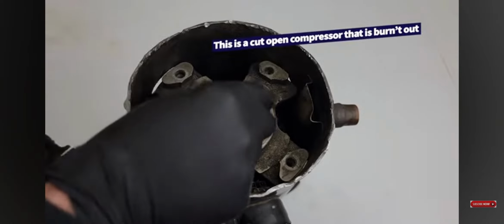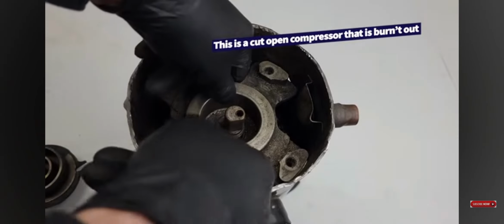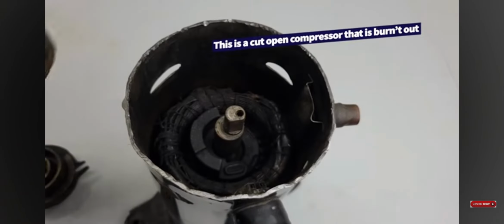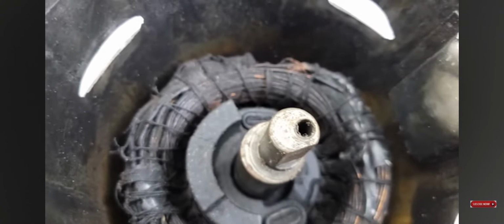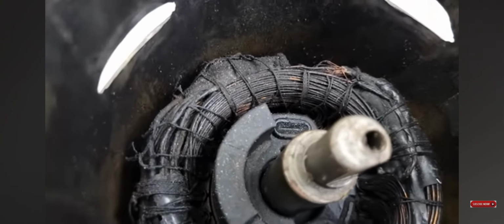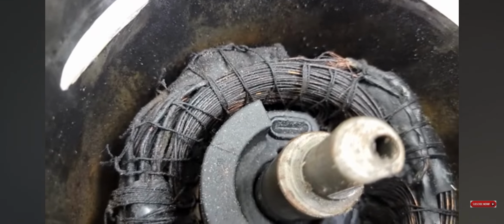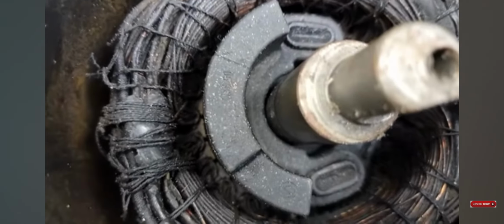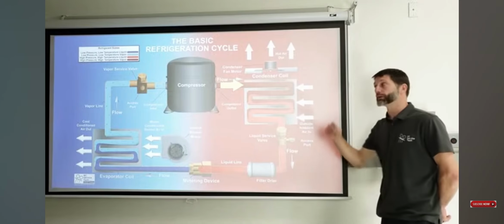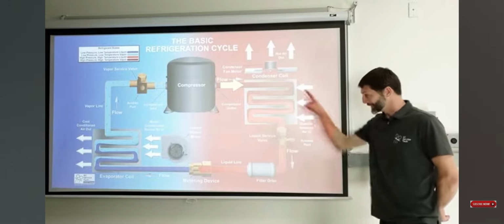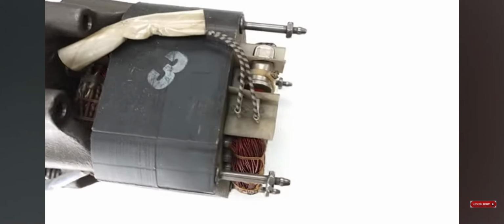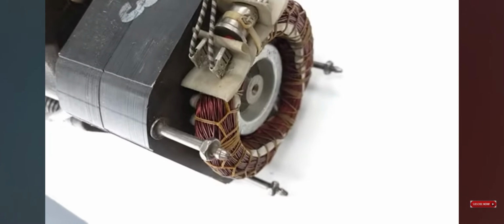So you got to think about that refrigerant and oil are traveling through any refrigeration system. That compressor is hermetically sealed, and so there's an electrical motor on the inside of there with electrical windings that are exposed to the refrigerant, because the refrigerant's job is not only to do this whole loop, but it's to also lower the temperature of the motor inside. It's to cool the motor.